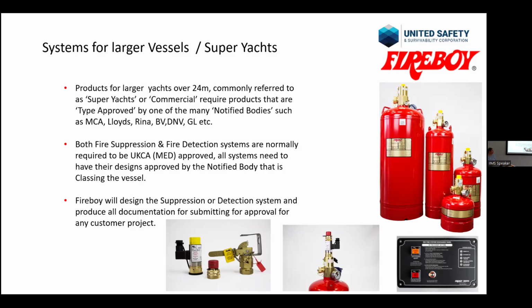These ones do fall under the same rules. Annual inspection required, must be by a third party, 10 years life as well. After 10 years, again, you need either hydrostatic testing or a complete replacement. In this case, I would probably say it's cheaper to do hydrostatic testing. On the smaller ones, it might not be worth going through that. Might be just better to replace it. Gives you 10 years of life instead.